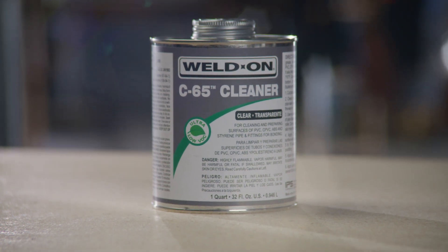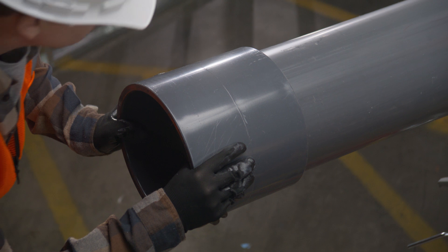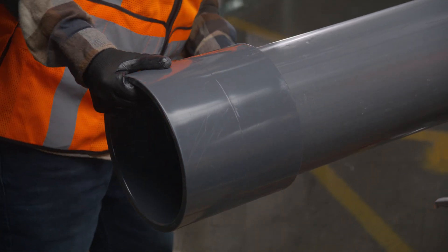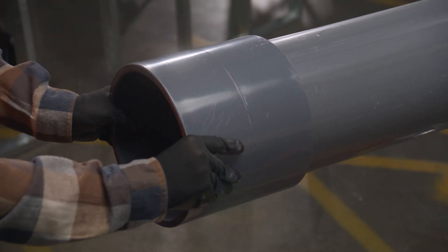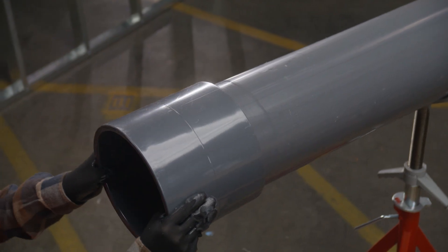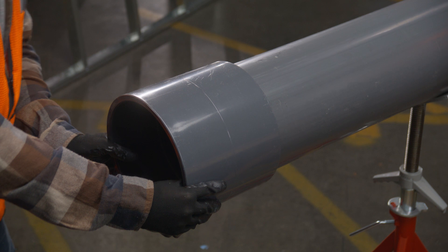Weldon has a variety of cleaners you can choose. Next, check the fit. A good dry fit occurs when the pipe enters the fitting at least one-third to two-thirds of the way into the socket without being forced. This dry fit should not be too tight or loose enough to jiggle. A wet fit occurs when the pipe bottoms into the fitting socket with no interference, but without slop.